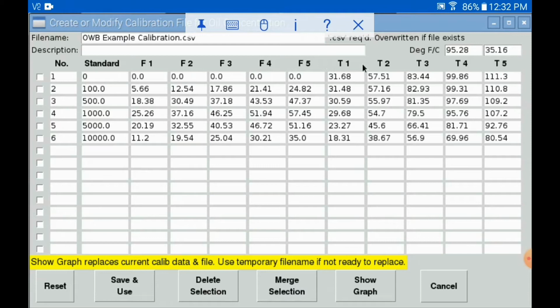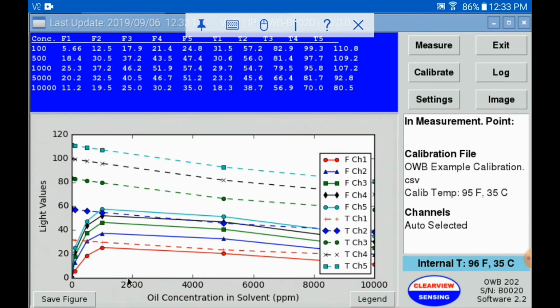The calibration file will show the value of each standard, fluorescence values, transmitted light values, and the temperature of calibration. Notice that fluorescence values increase to a point, which is the peak fluorescence, and then decreases. Transmitted light values start at a maximum and decrease to a minimum. Please click Save and Use to activate the calibration file and return to the GUI.